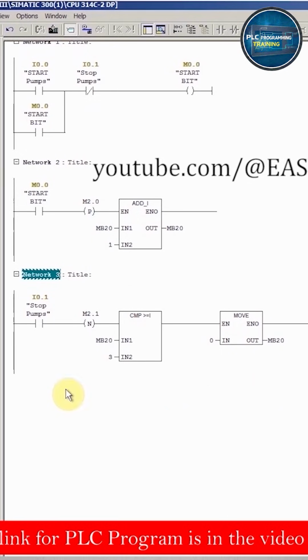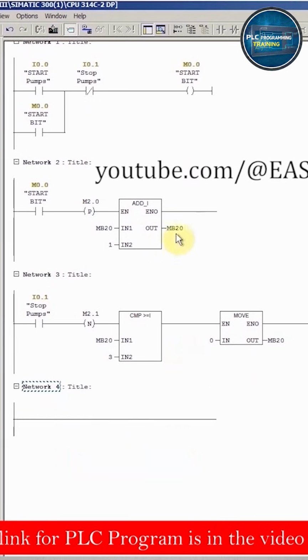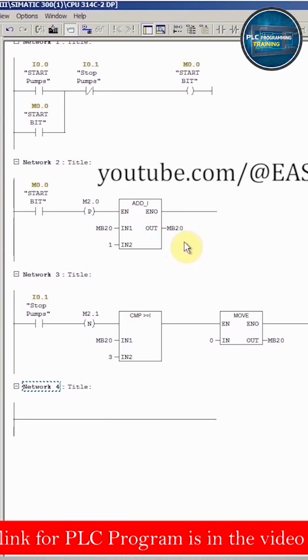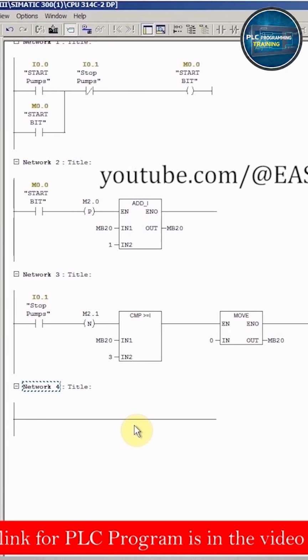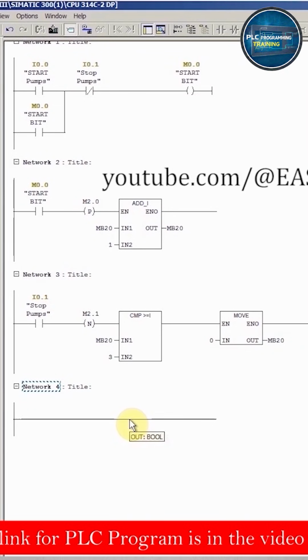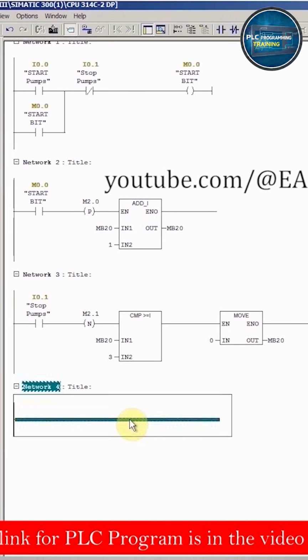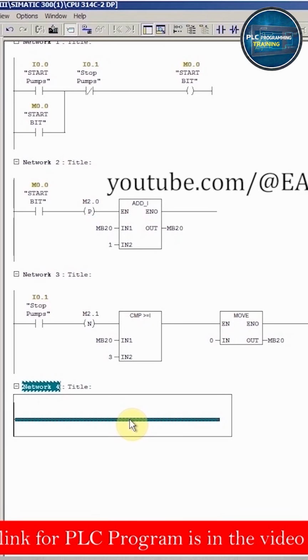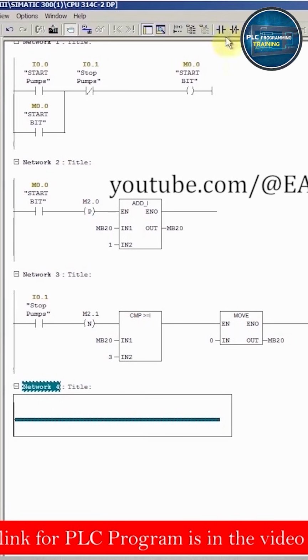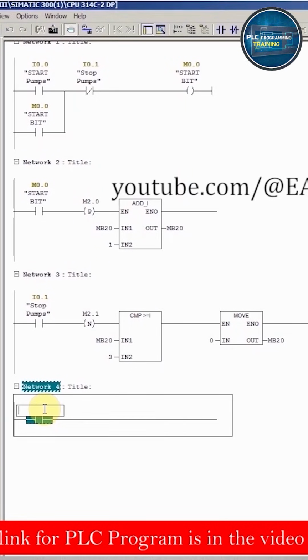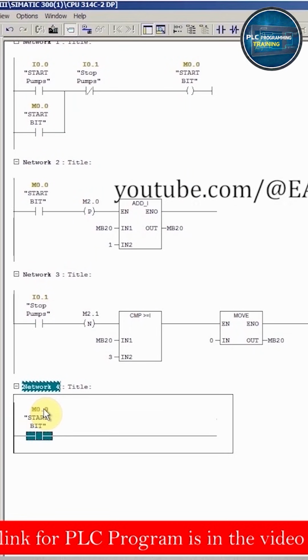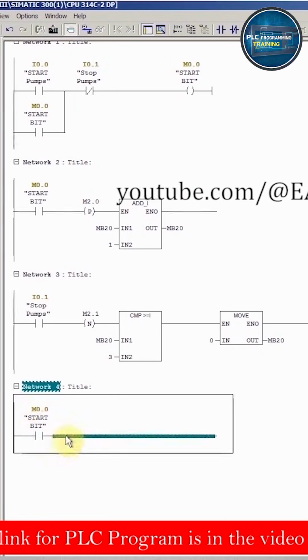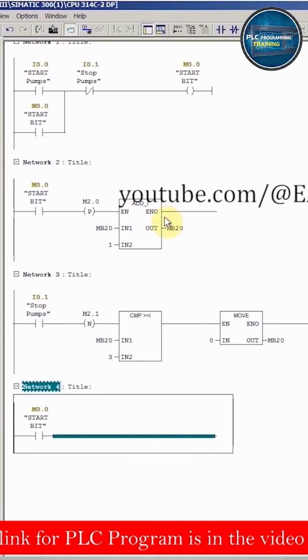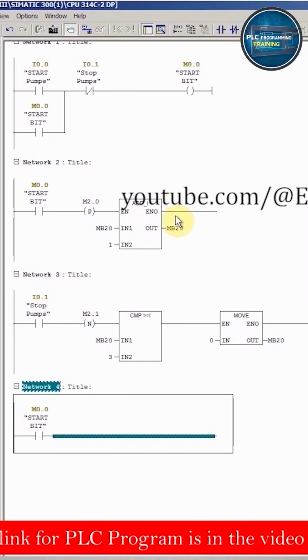So in the next network, we will use the value of this MB20 byte to turn on the pump and change the duty cycle of these pumps. So now let's write the logic to change the duty cycles for these pumps. For this one, we will use the bit M0.0, which is our start bit. And the next thing, we have to compare again the value of this memory byte 20. But this time we will insert an equal to comparator.